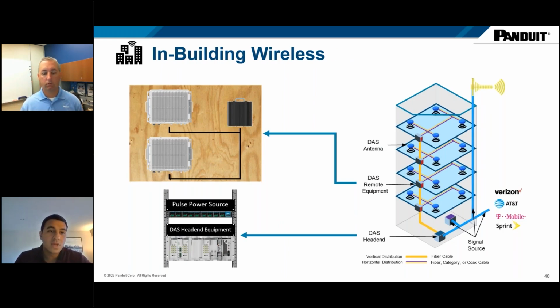just a touch on how this would actually look in a building. So if we look at in-building wireless, or if you're familiar with DAS, distributed antenna systems, this is a primary application for this. Typically, in a DAS design, if you think of a building, you have a head-end room, and in that head-end room, you have DAS head-end equipment that's pushing communication up through fiber to radios that are located around the building. And with a class 4 system, you could have the source reside in the head end. You can push the class 4 power up the class 4 cable alongside the fiber or in a hybrid cable to these remote locations. That copper would hit the converter, and the converter would then provide power out to your radios.